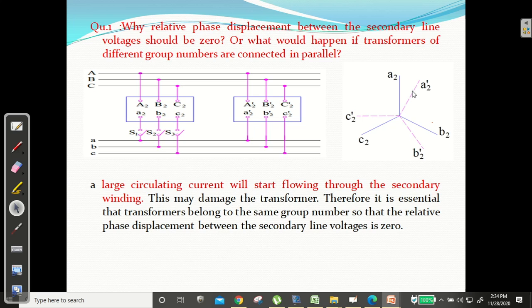Clear? So what will happen? Suppose you draw the instantaneous voltage like that, one is like this, the other has a phase difference like this. Because of the phase difference, this is the voltage difference between the two, A and A2 dash, B and B2 dash, C2 and C2 dash. So what will happen? Because of that, large circulating current will start flowing through the secondary windings. This may happen, and this may damage the transformer.